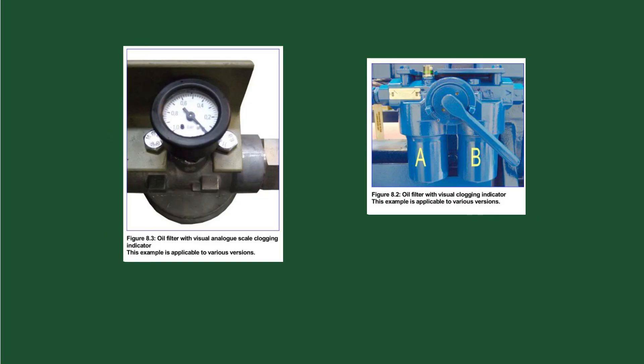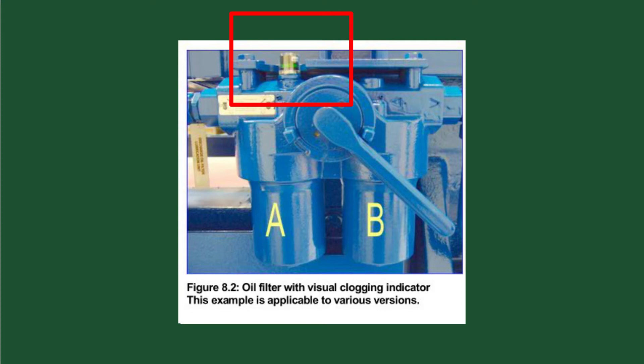M2 and M6 filter housings are equipped with a visual clogging indicator. Under normal operation, the indicator will show a green display. If the indicator displays red, then the oil filter resistance is too high and needs to be replaced immediately.